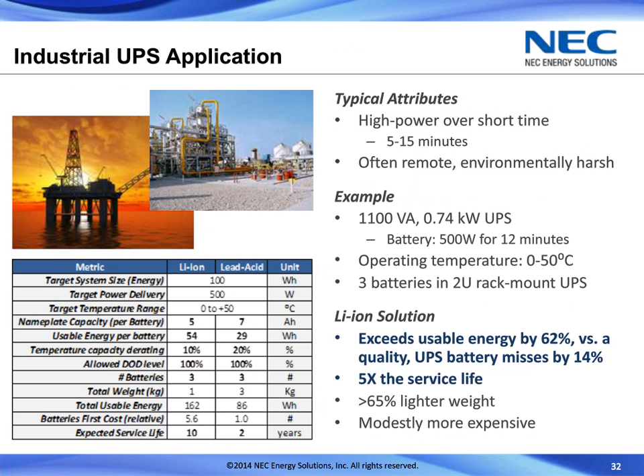So the third application, industrial UPS. Typical attributes: very high power, between 5 and 15-minute discharge times, remote, environmentally harsh. So for this example, we went with 500 watts for 12 minutes. So that's actually a 5C discharge rate, which is very, very high, certainly for lead. It's within the range for lithium, but still on the high end of that.